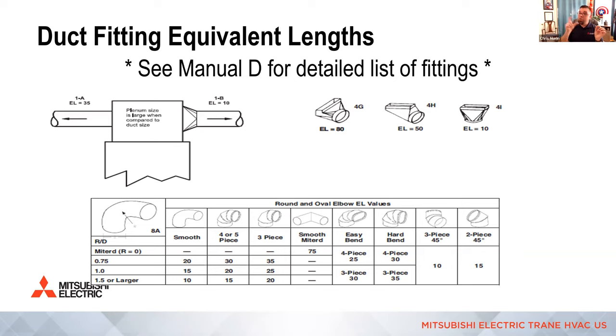So if you have a 120-foot fitting, which is a bullhead T, then that would be a 0.12 pressure loss like we talked about earlier, okay? Same thing applies on the bottom here when you talk about a smooth 90 compared to a 4 or 5 piece or a 3 piece. You can see as we make it harder for the air to make the turn, the equivalent length value goes up. And it all depends on the mitered turn, the radius, right? That's what determines the equivalent length value.